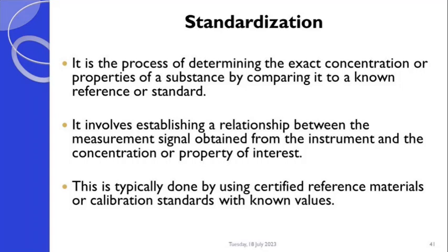When we analyze this certified reference material and compare the signal coming from the instrument to the known concentration of the lead, we can establish what we call an equation or a calibration curve, where we relate the instrument responses to the concentration of the lead in the water sample.